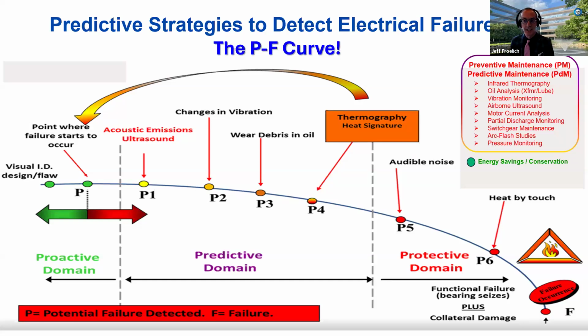But once it gets hot to the touch, you're in a potential immediate, imminent danger situation, and you get to eventual failure, at which point you may be talking electrical incidents with significant energy, like an arc flash, or mechanical failure, where you have a seized bearing and a machine that's going to abruptly stop. So I've included several of these different predictive and preventive maintenance type programs in the upper right.